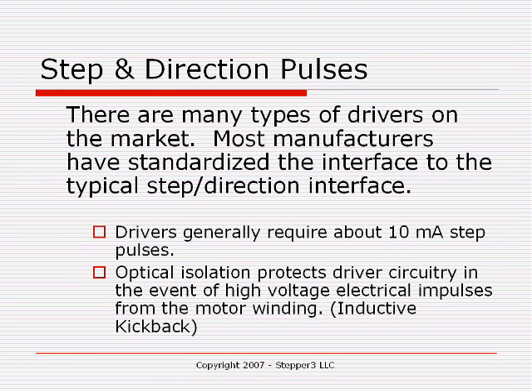The direction signal is also a TTL level pulse. The step signal is a series of pulses; for each pulse, it moves the motor a specific increment. The direction signal is either high or low — high meaning the motor will go one direction, low meaning it will go the opposite direction.